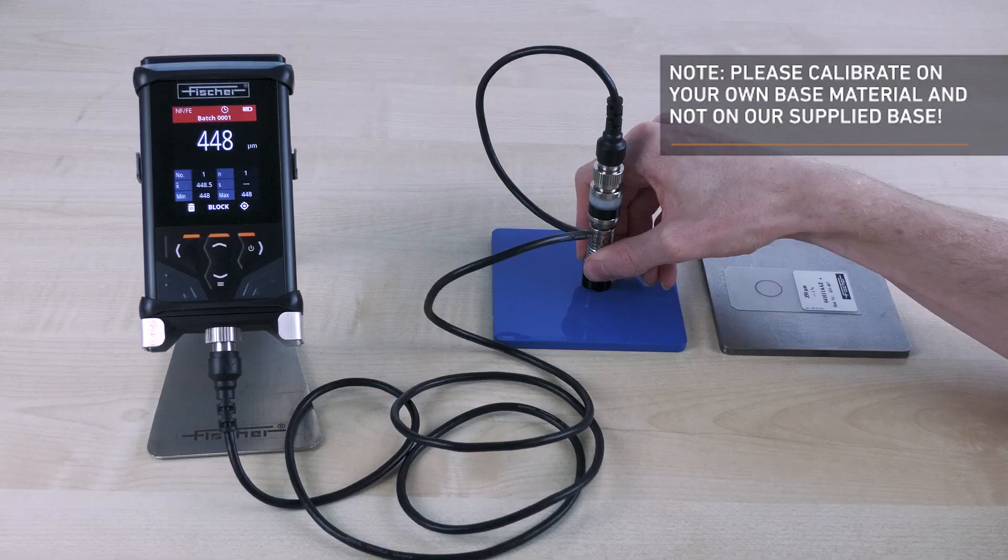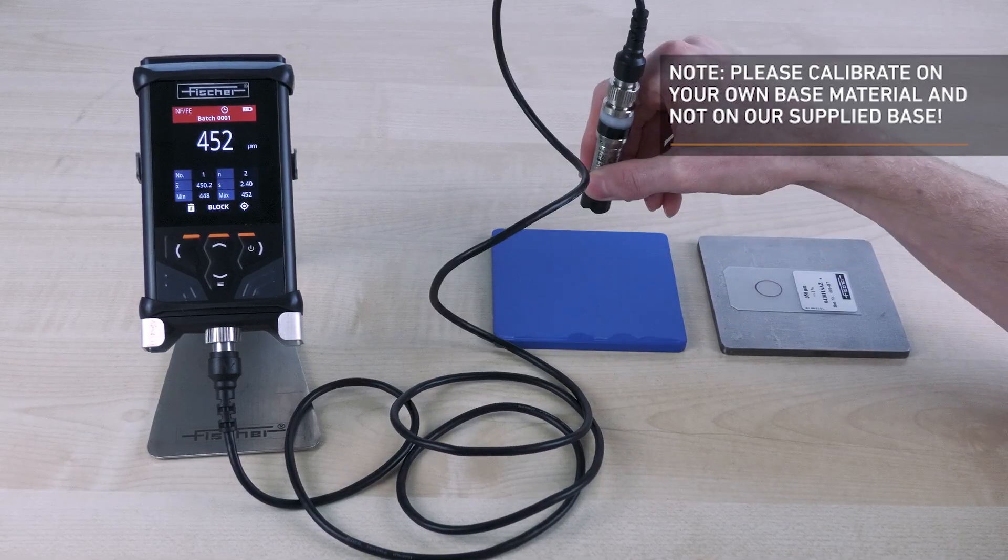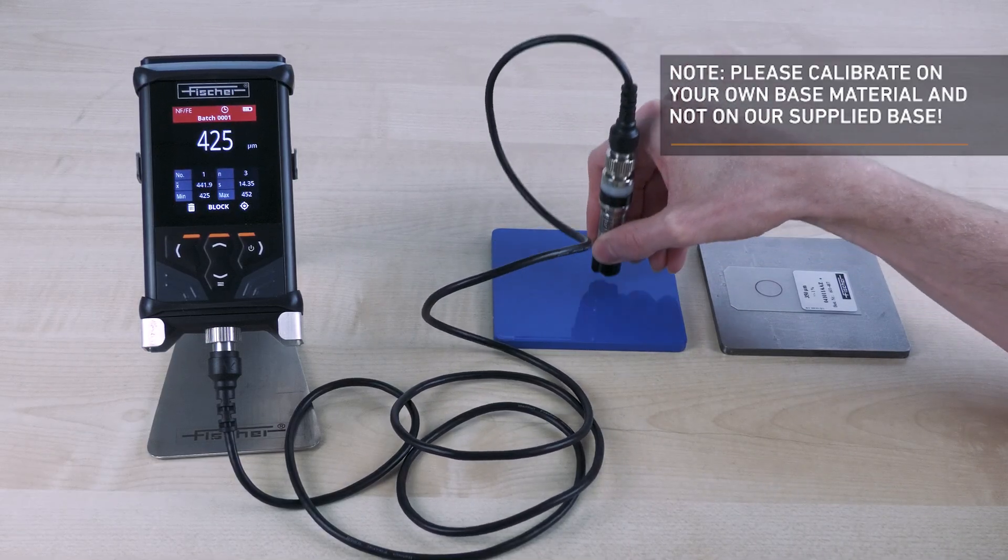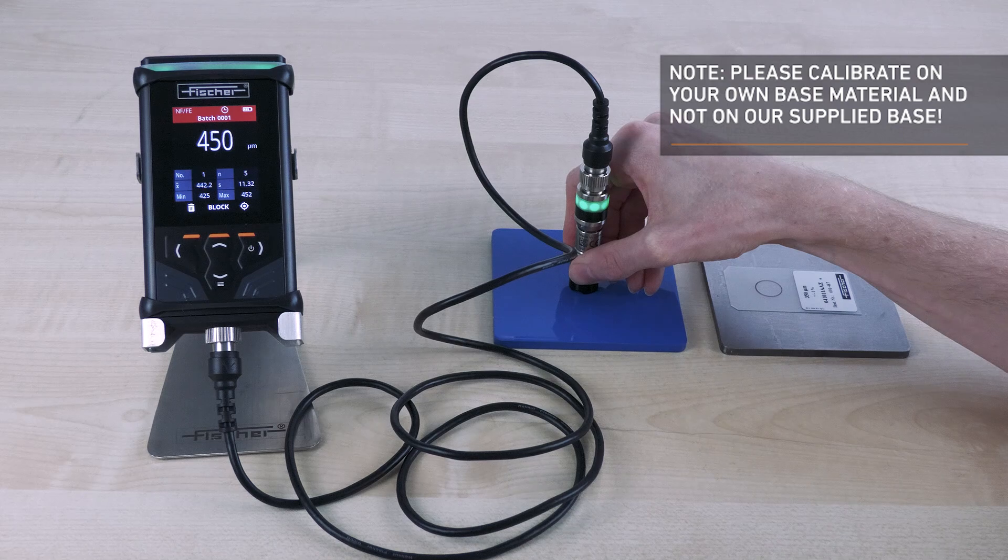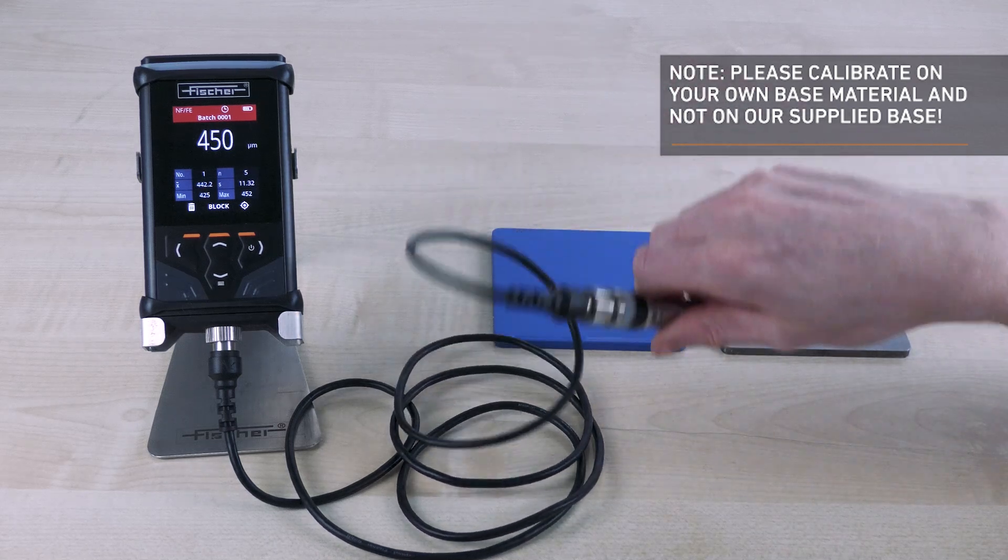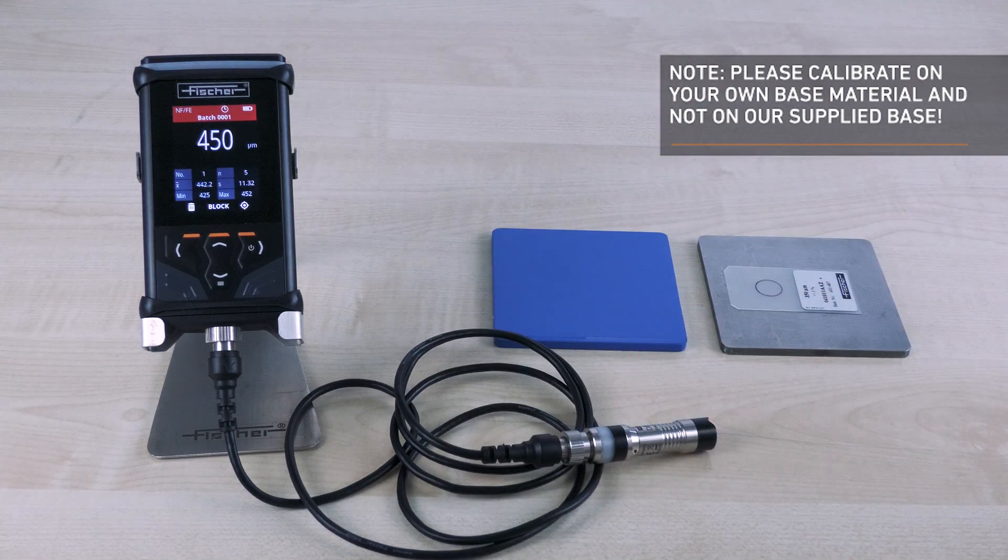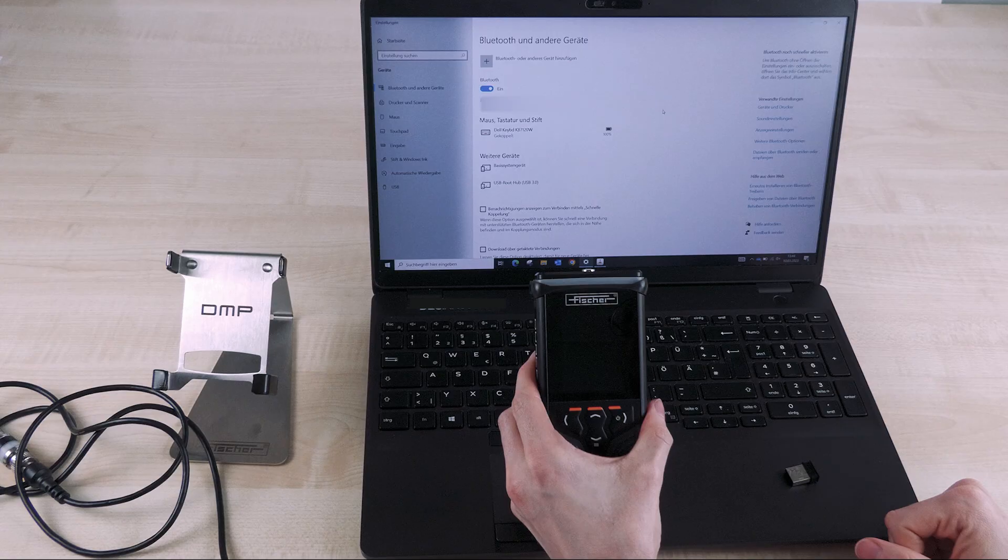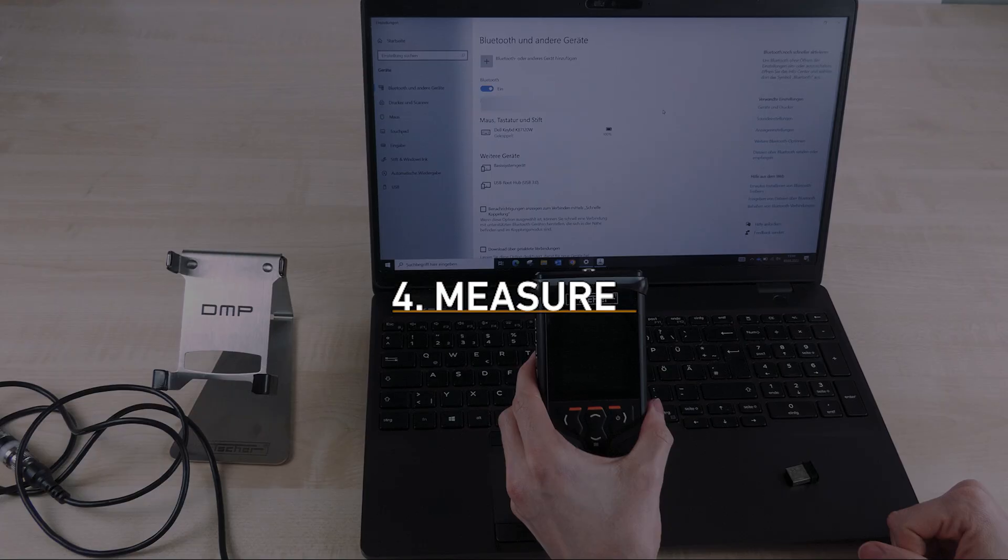In the next step, check the calibration by measuring on the coded test piece. You get the maximum security of your measuring results by our CAL check function. This checks your currently used calibration quickly and at any time. The measuring device is set up and calibrated so you can start taking measurements.